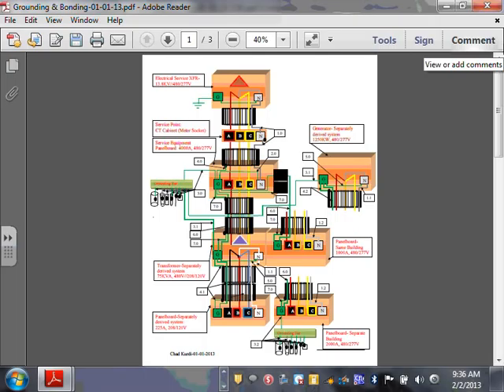Yes, sir. If you have a delta, you still got to carry a neutral inside whether you use it or not. But you don't have a neutral if you have a delta. Well, you got to carry a wire inside. If you have a delta, and the code says if you have a grounded conductor, if a system is grounded, the only time you have a grounded conductor, aka the neutral, is if your system is grounded. If you're getting a delta, the only thing you will carry from the transformer up to your building is really three-phase conductors. That's it, by code. You don't have to carry the neutral, because the neutral does not exist. You know what I mean?